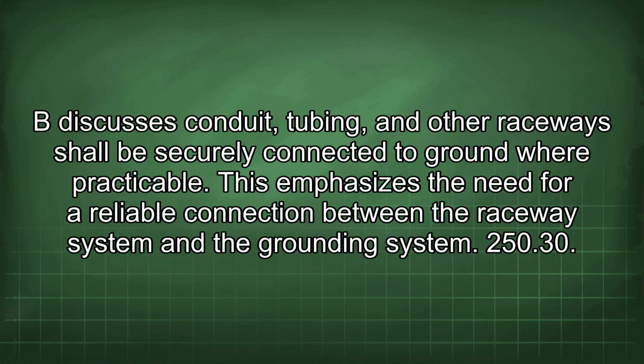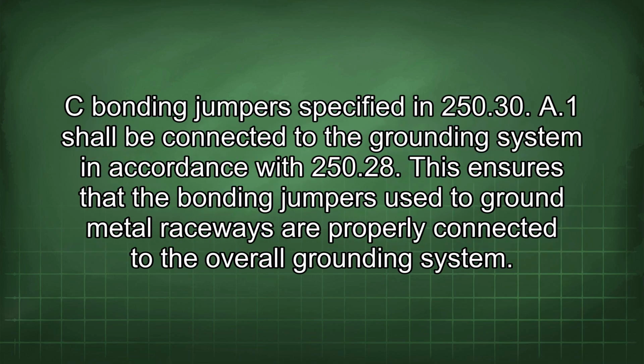250.30 B discusses conduit, tubing, and other raceways shall be securely connected to ground where practicable. This emphasizes the need for a reliable connection between the raceway system and the grounding system. 250.30 C, bonding jumper as specified in 250.30 A1, shall be connected to the grounding system in accordance with 250.28. This ensures that the bonding jumpers used to ground metal raceways are properly connected to the overall grounding system.